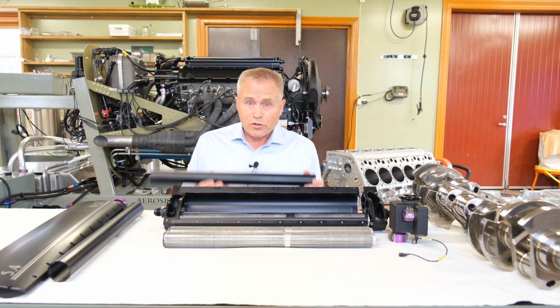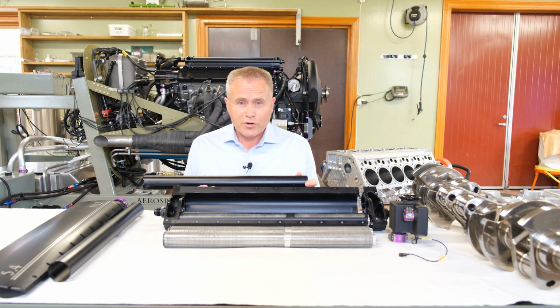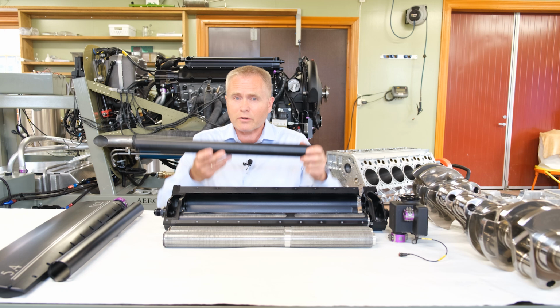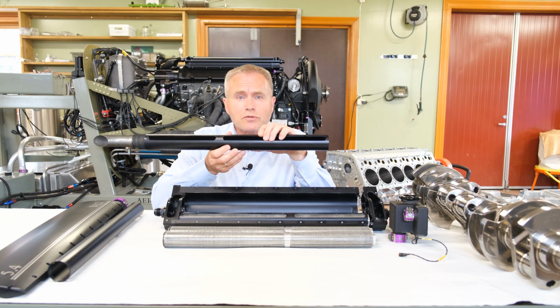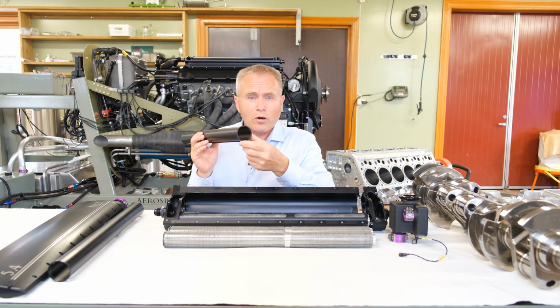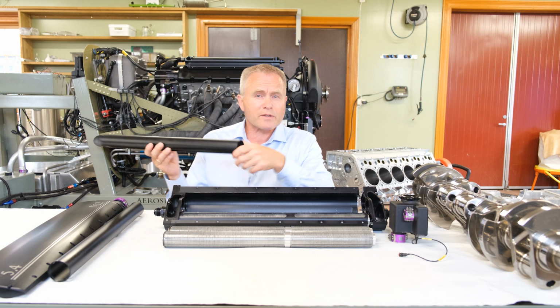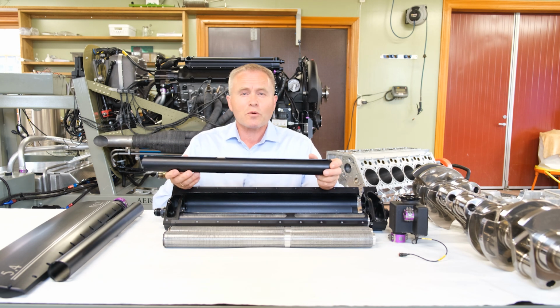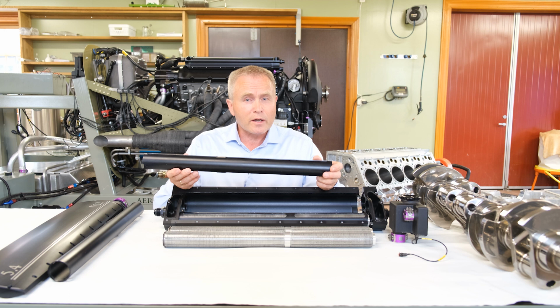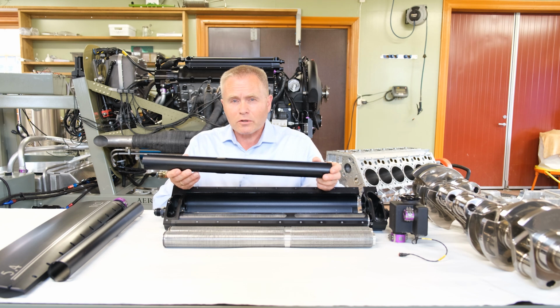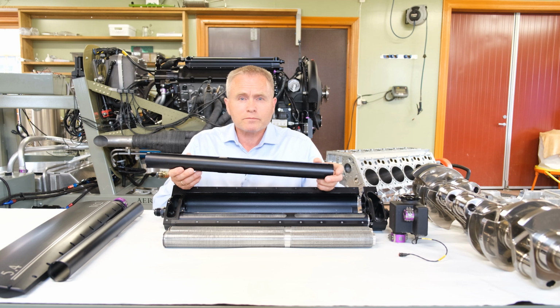When the shield is installed around the heat exchanger core, the pressurized hot air is forced through most of the circumference of the heat exchanger, which makes the hot air stay in full contact with the cooler fins in the core, and also for a longer period of time. And this really helps increasing heat transfer. So the shield or the tube is a quite important feature for effective heat transfer in this system.